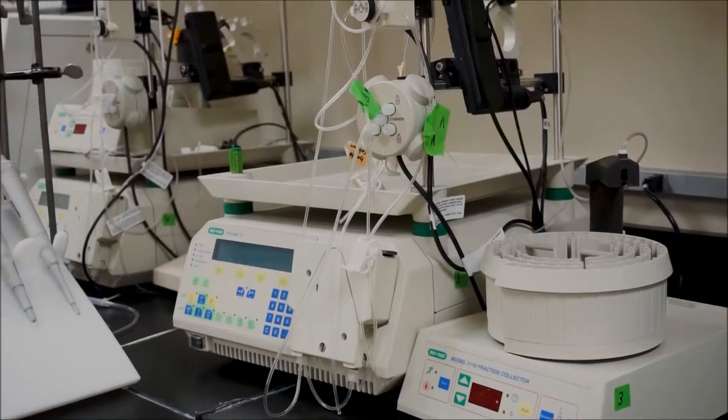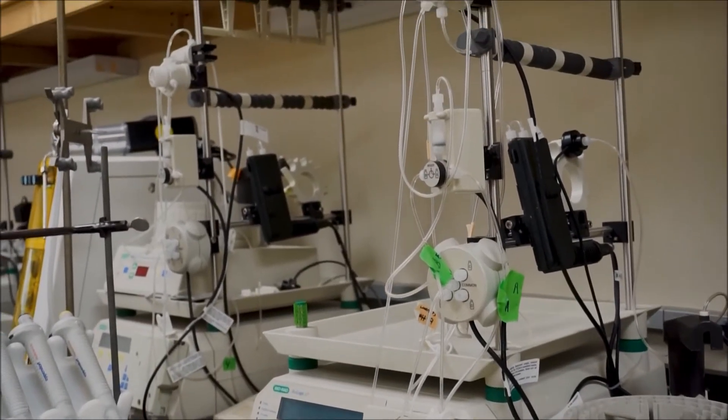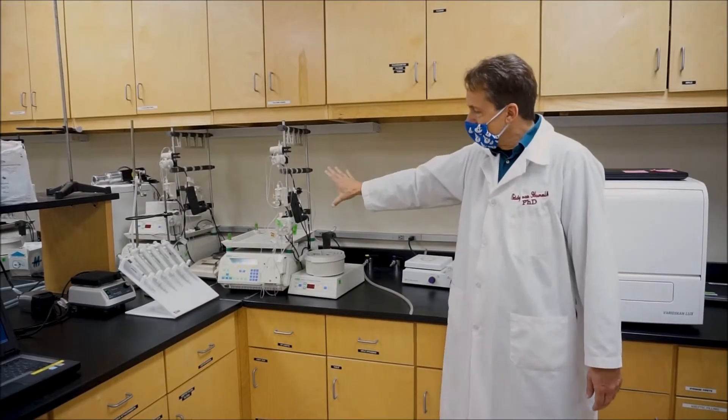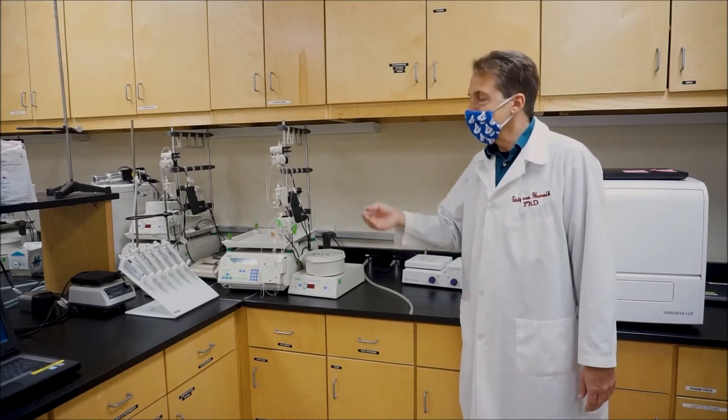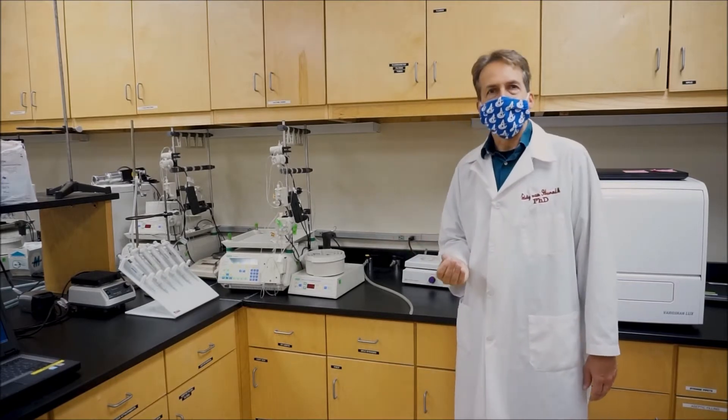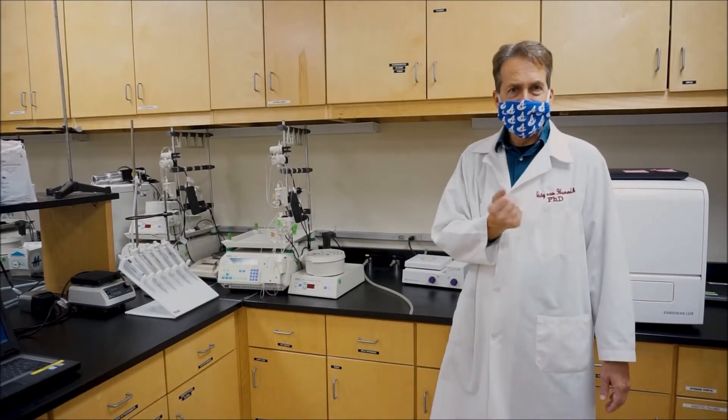Over here we got a smaller brother of the HPLC. This is an FPLC. It's not built up at this moment, but this is basically where we do affinity chromatography and other materials to make sure that we can purify before it goes into the HPLC.